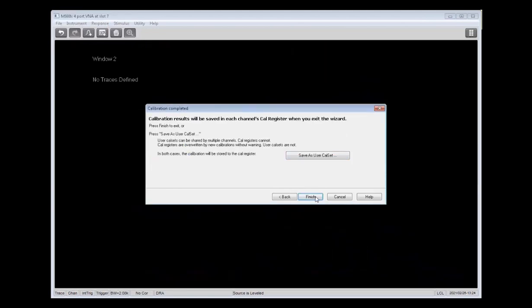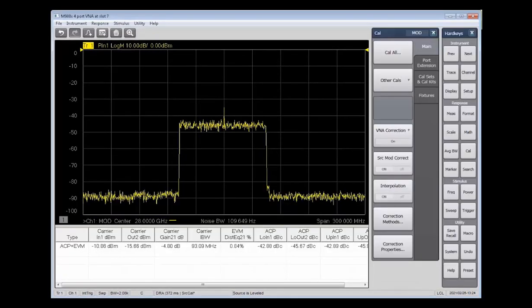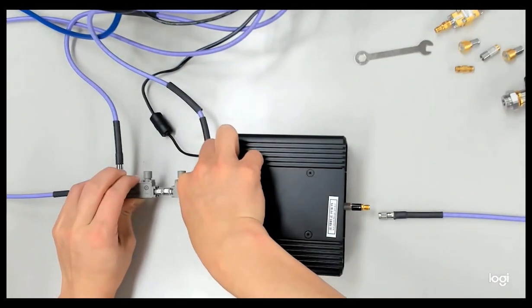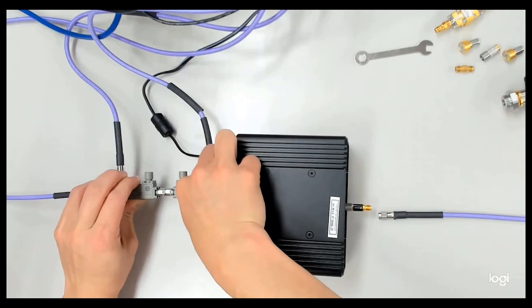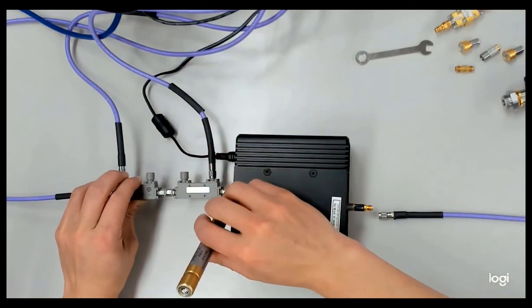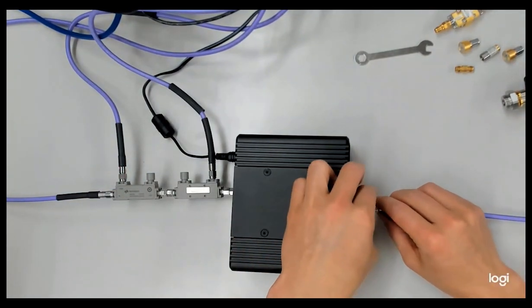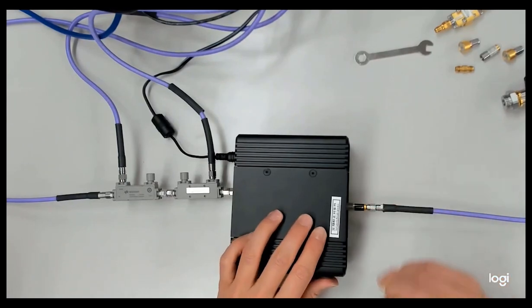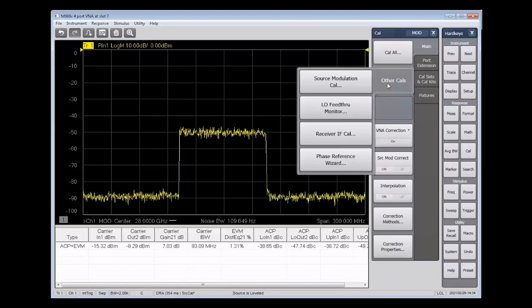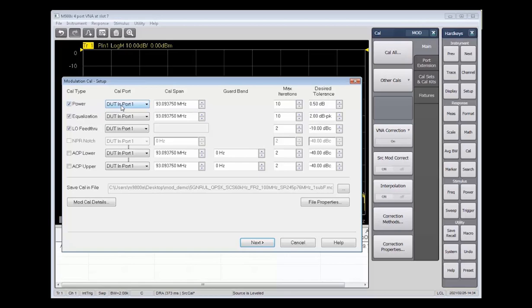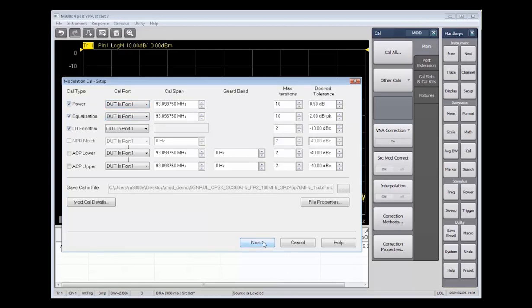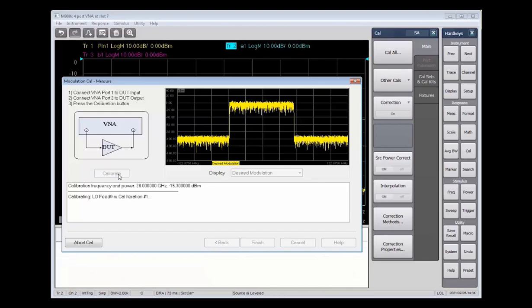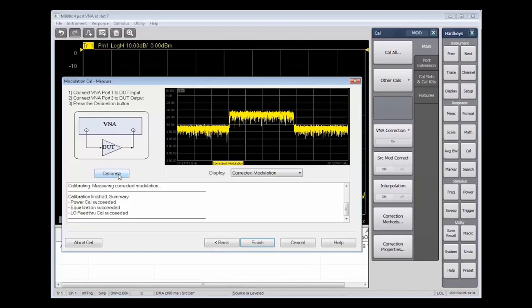Once the electronic calibration portion is finished, then we're done with our S-parameter and power calibration, and we're ready to connect the device so that we can perform the source modulation calibration. So here's our amplifier again. We're going to connect ports 1 and 2 of the amplifier to ports 1 and 2 of our test system. And this is a powered amplifier, so you can see there's also a power cable connected to it. Now for the source modulation Cal, we'll go to Cal, Other Cals, then Source Modulation Cal. Make sure that Power, Equalization, and LO Feed-Through are checked, then click Next. We've already connected our DUT, so we will click Calibrate. And then once this calibration finishes, we are finished with calibration completely, and we're ready to perform some measurements.